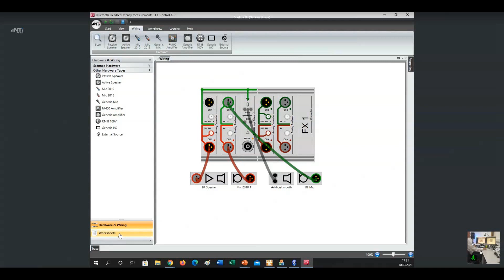So let me swap over to the software. Here you see again the wiring, the FX100, here connection to the loudspeaker, small loudspeaker in the headset and the Bluetooth device. This is the measuring microphone connected to the FX100. I have a reference loudspeaker connected to the instrument, and this is the microphone of the headset, which is fed back to the FX100 for the measurement. So here we have the worksheet where the measurements are executed. We have prepared a sequence, and I will start that right now.